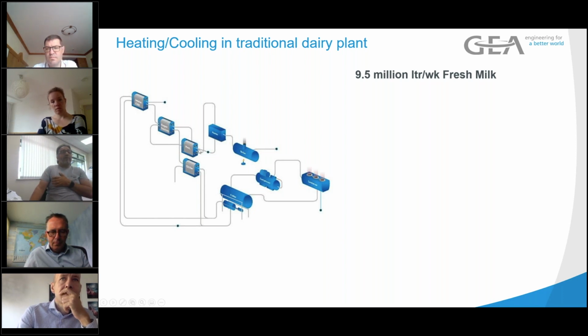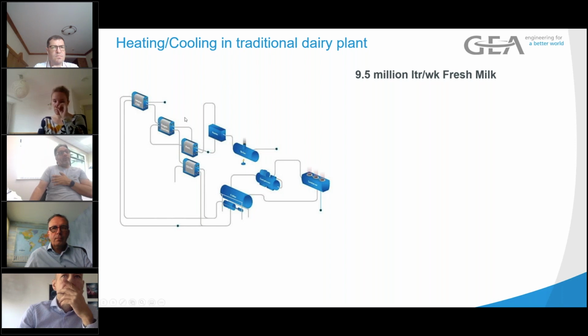So they have a recovery rate on a pasteurizer where the hot milk leaving transfers heat to the cold milk coming in, and they're normally 90–92% efficient, which means you have to inject heat to get the milk up to the pasteurization temperature, which on milk is about 72 degrees, or fresh milk or cream 74, 76, something like this. But the process is whatever you put in kilowatts, and let's say it's a megawatt, you have to remove that megawatt at the other end via the refrigeration process.